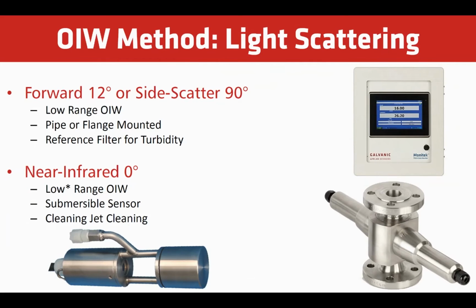Near-infrared submersible sensors can also be used for oil and water. While these sensors are equipped with cleaning jets to handle higher concentrations of oil and water and avoid maintenance issues, they're best for lower ranges.